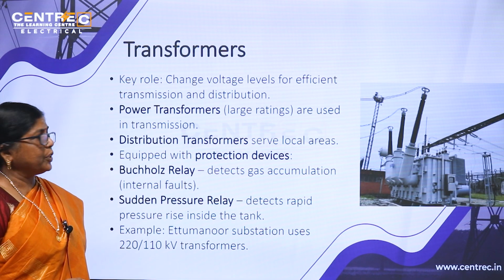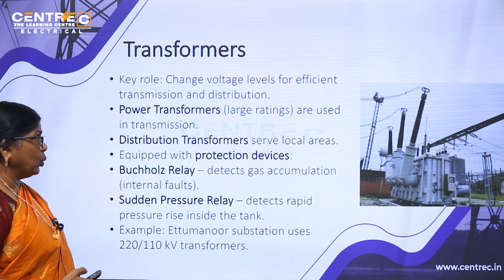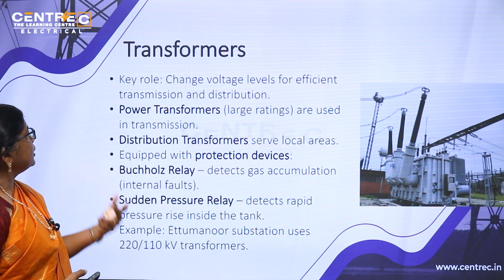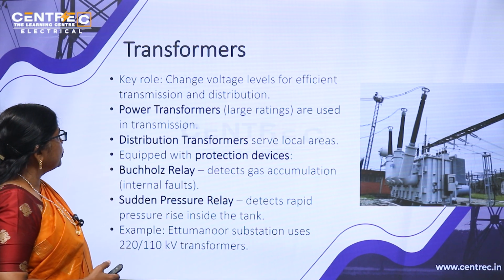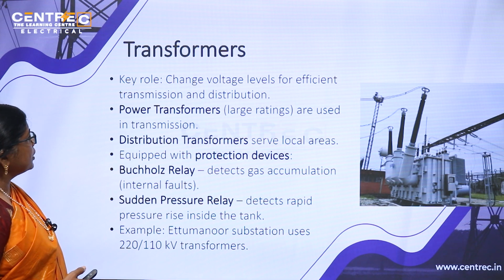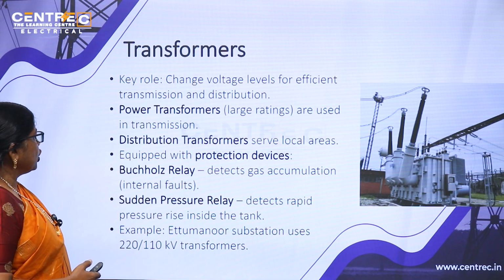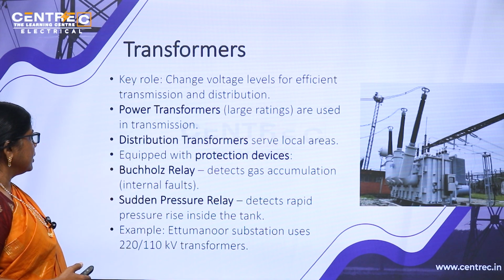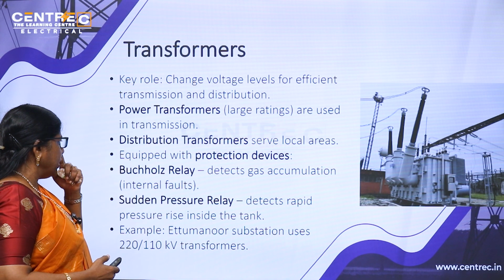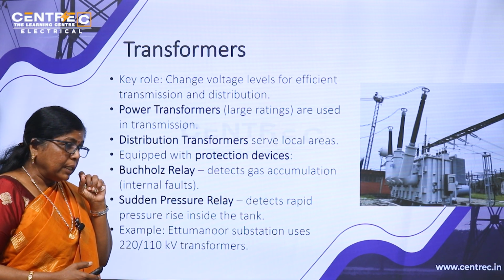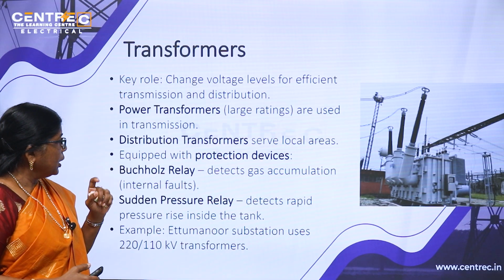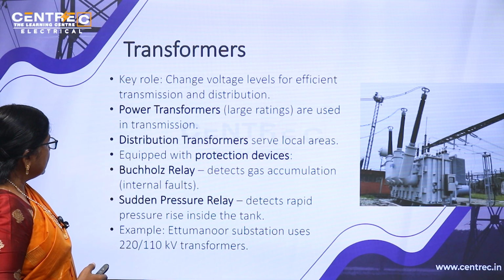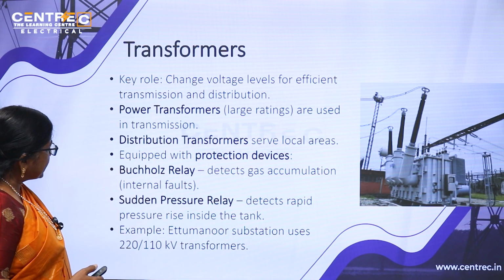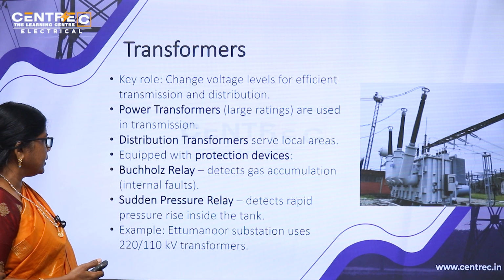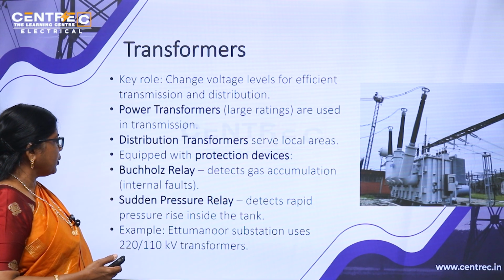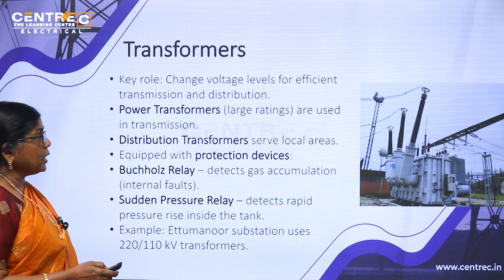Transformers, these are power transformers actually. Key role: change voltage level for efficient transmission and distribution. Power transformers are used in transmission. Distribution transformers serve local areas. Equipped with protection devices. Buchholz relay detects gas accumulation from internal faults. This is the only relay which is used in transformers above 500 kVA. Then sudden pressure relay detects rapid pressure rise inside the tank. For example, Ettumanoor substation uses 220 and 110 kV transformers.